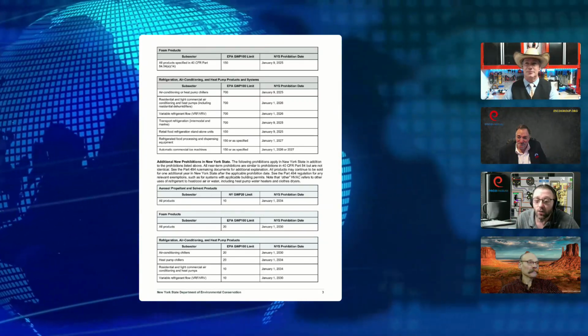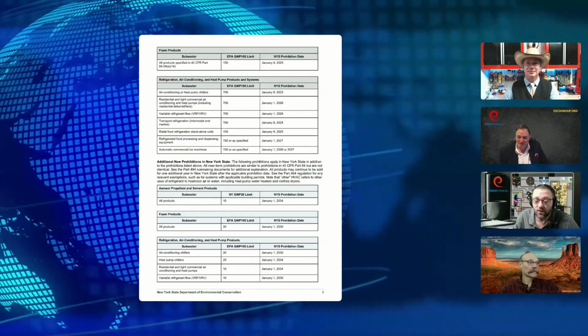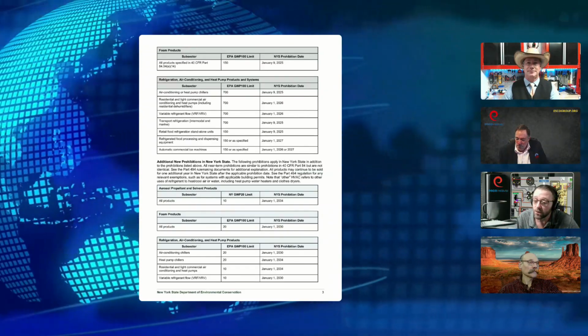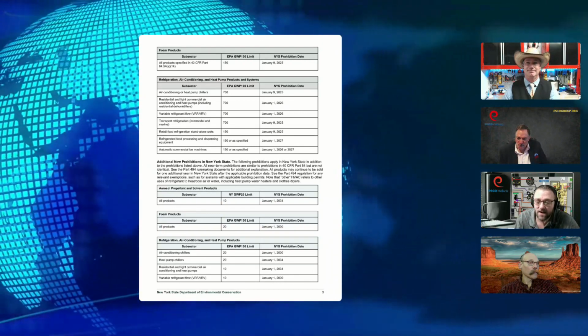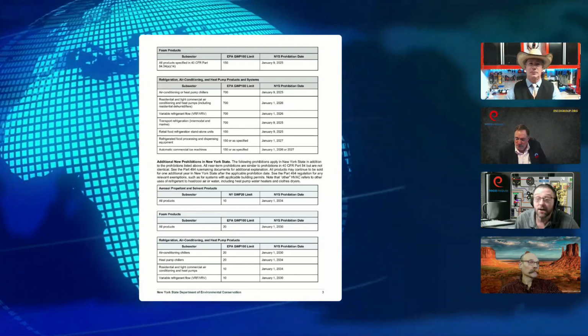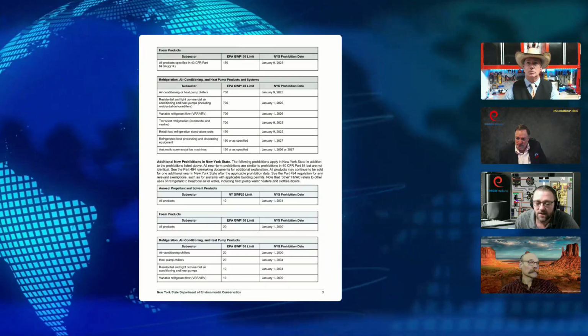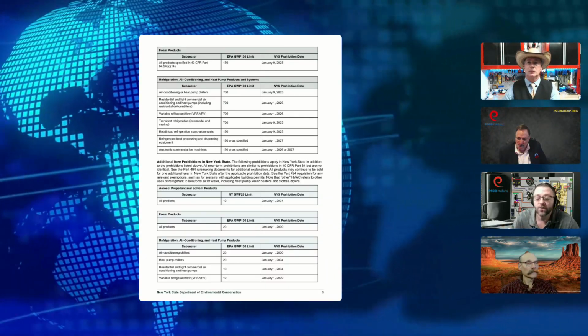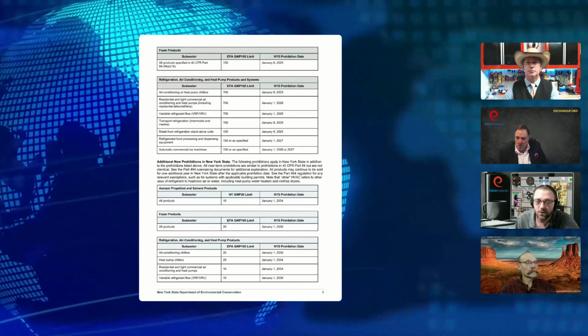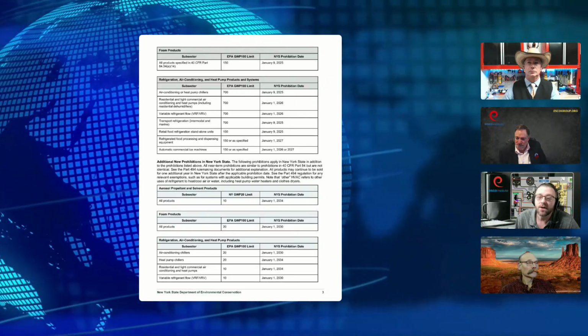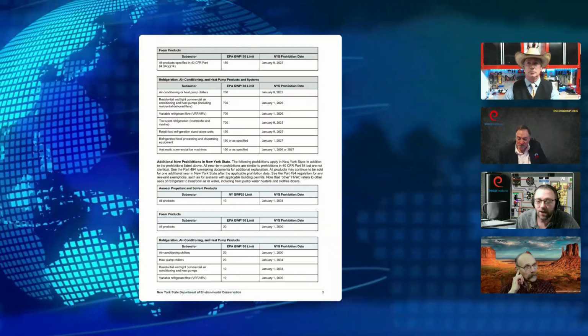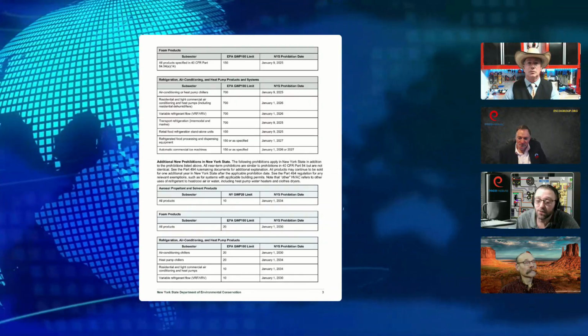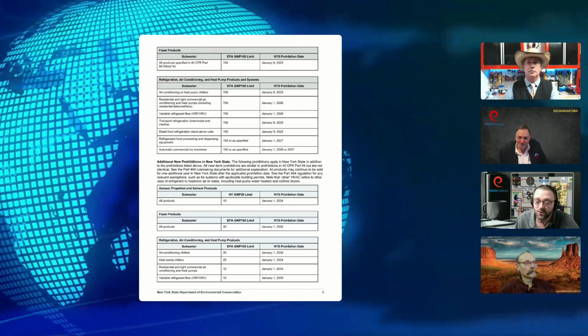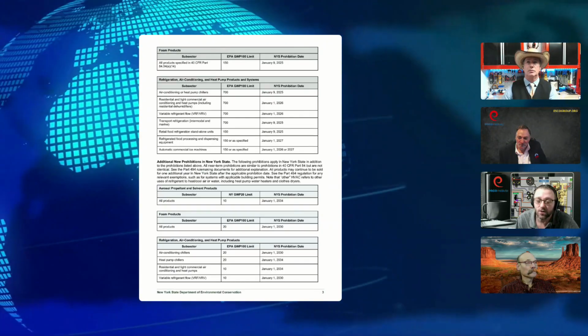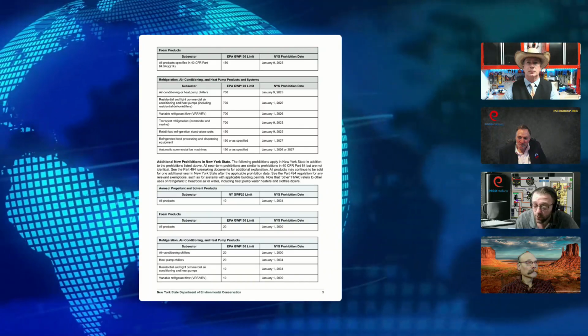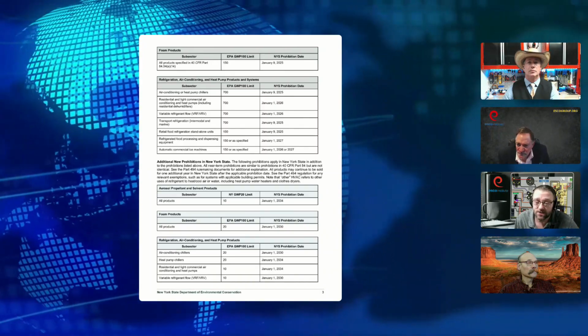As we saw with the A2L transition, different states are at different levels. Some states were still using building codes from 2007 and had to update their standards to allow installation of A2L systems. We're going to have to do it all over again in a few years, because as mentioned, there's a monoblock propane system out there, but by building code today, it couldn't be put in a residential application. There's no standards for that, it's not allowed by code. A lot of changes have to be made between now and then to ensure this transition takes place.